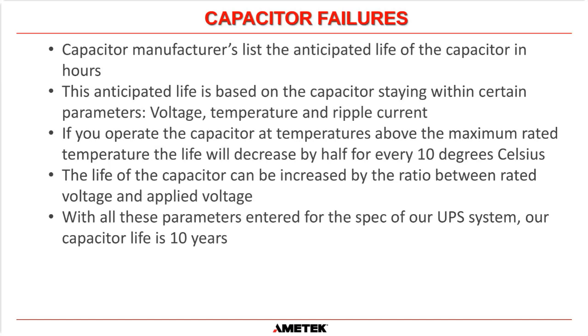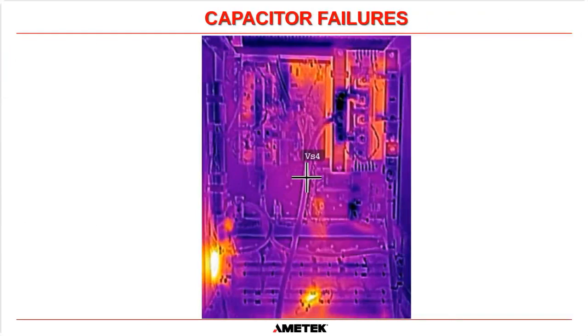And also the life of the capacitor can be increased by the ratio between the rated voltage and the actual applied voltage. So if you have a capacitor that's put on a system that is rated for 1,000 volts, but is only going to see maybe a maximum of 400 volts, then you can actually increase the life of that capacitor according to the manufacturer's data sheet. Basically, when all of these parameters were entered into the specs for our UPS systems, the capacitor life works out to just about 10 years, okay? So that is why we recommend our capacitors are replaced every 10 years.